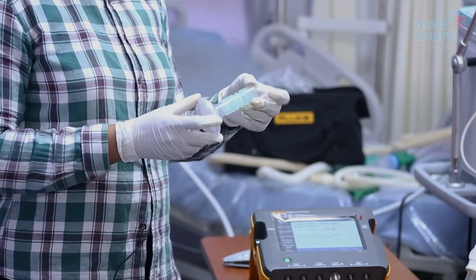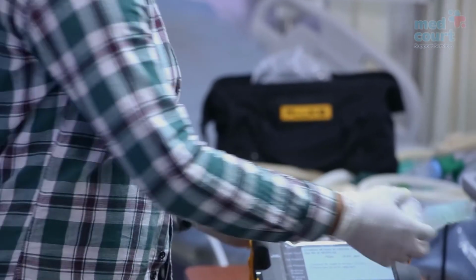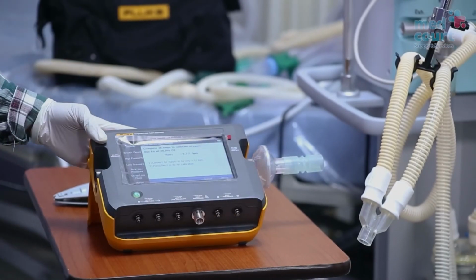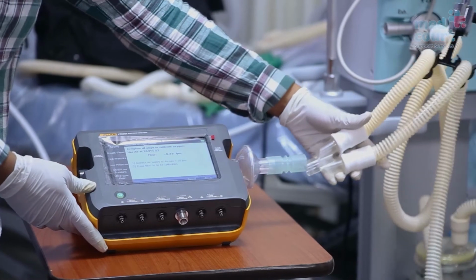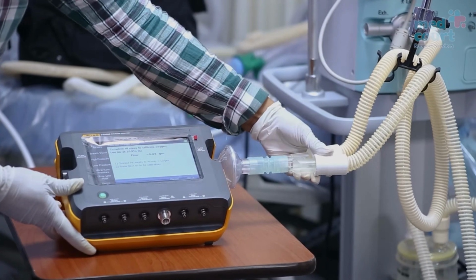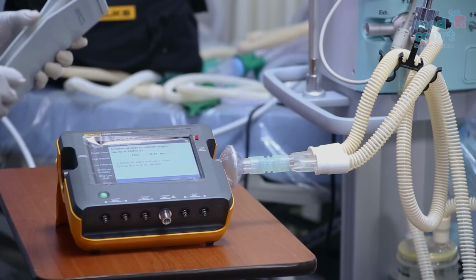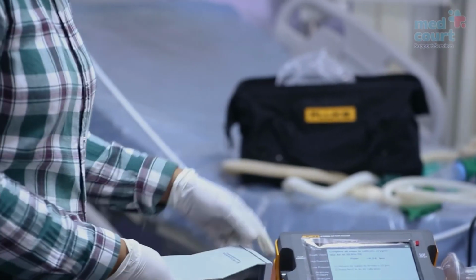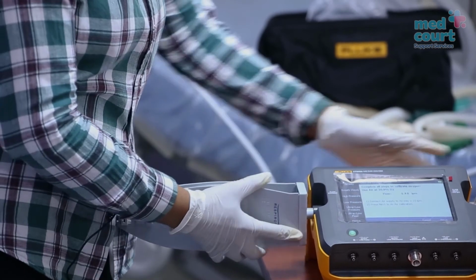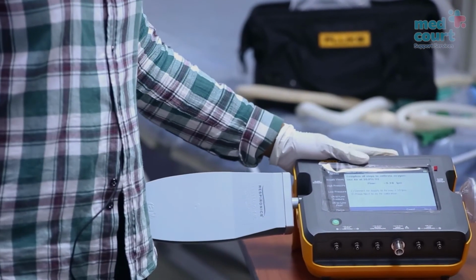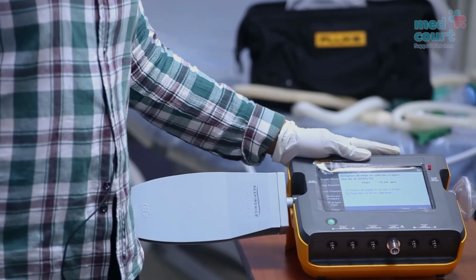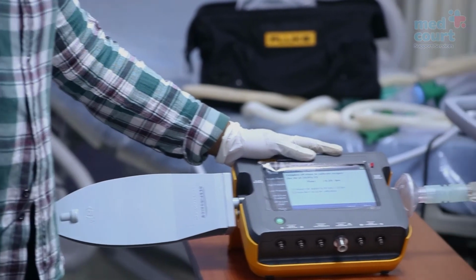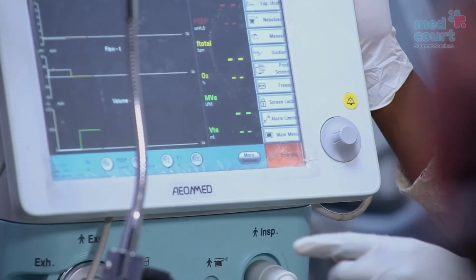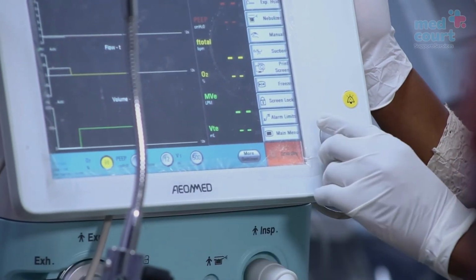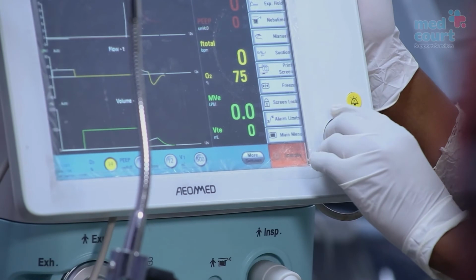Connect the adapter to the bacterial filter and to the flow inlet of the VT900A. Connect the Y-piece to the VT900A and the test lung with a stated compliance to the flow exhaust. Set the oxygen concentration on the gas flow equipment. So to calibrate for our 21% oxygen, we'll click on the O2 percentage to 21%.